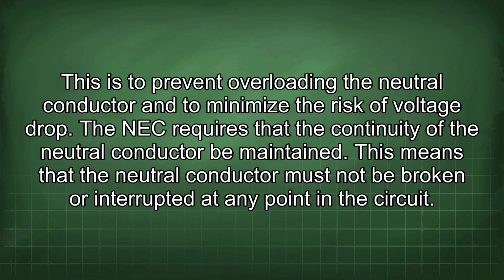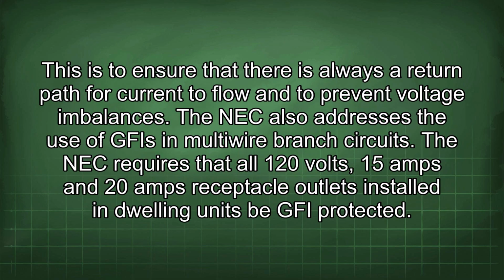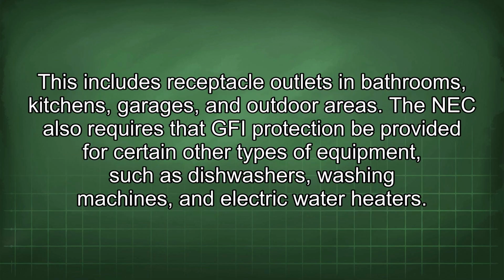The NEC requires that the continuity of the neutral conductor be maintained. This means that the neutral conductor must not be broken or interrupted at any point in the circuit. This is to ensure that there is always a return path for current to flow and to prevent voltage imbalances. The NEC also addresses the use of GFI in multi-wire branch circuits. The NEC requires that all 120 volts, 15 amps and 20 amps receptacle outlets installed in dwelling units be GFI protected. This includes receptacle outlets in bathrooms, kitchens, garages, and outdoor areas.